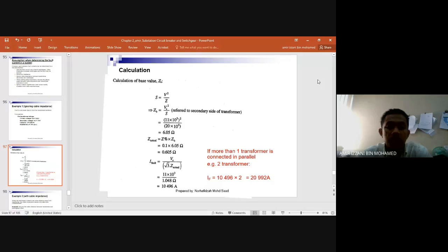Firstly, we need to determine the impedance of the transformer, by using this equation, S equals V squared over Z. Refer to the secondary side of the transformer, so V secondary is 11 kV. So 11 kV squared over 20 MVA, and we get 6.05 ohm.